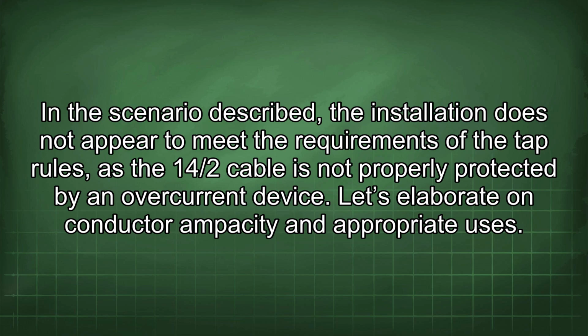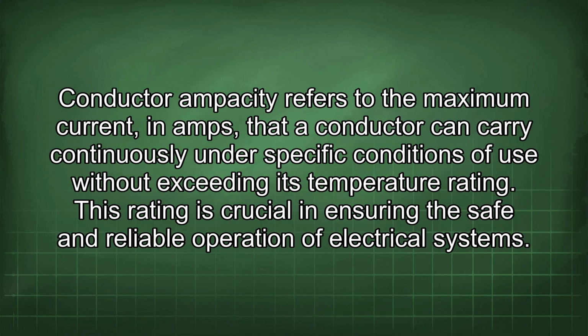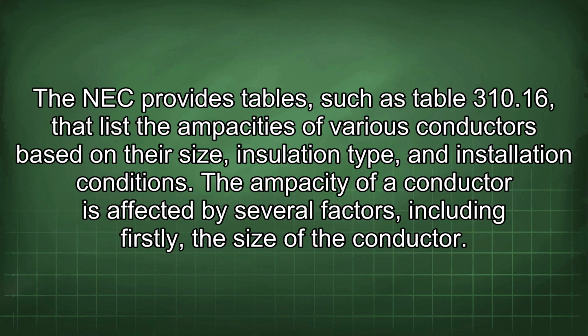Let's elaborate on conductor ampacity and appropriate uses. Conductor ampacity refers to the maximum current, in amps, that a conductor can carry continuously under specific conditions of use without exceeding its temperature rating. This rating is crucial in ensuring the safe and reliable operation of electrical systems.